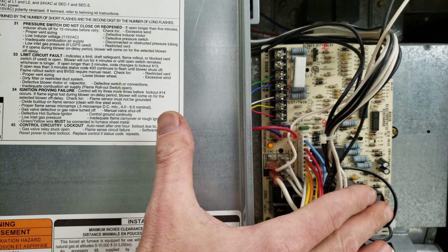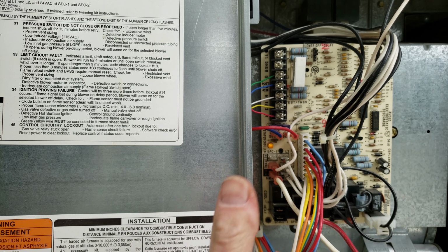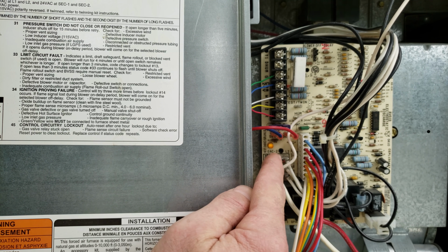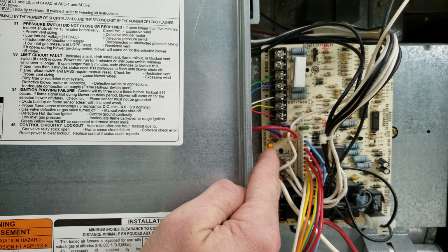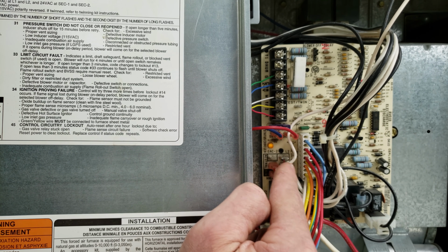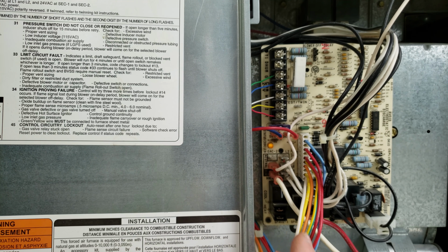At least with a gas furnace, you have a status code light on the control board for furnaces that are, say, 20 years old or newer, and that at least gives you a place to start. Now, if that status code light is not flashing an error code, it's very likely that your intermittent problem has to do with the thermostat wiring, or the thermostat, possibly the control board.